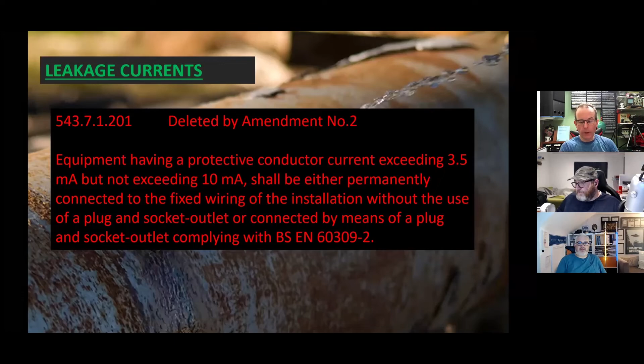But yes, you're right. It does link into this deleted by amendment without a doubt, because it also links into the regulation that covers the leakage on each individual circuit not exceeding 10% of the rating of the RCD. Why would you need 3.5 to 10 milliamp anymore on a reg? You don't need it. So it's effectively gone. There is also one last thing. This one here, this is rowed about so much, guys. 543.7.1.204. It's another UK reg. This has also been deleted, and it's where two protective conductors are used in accordance with 543.7.1.203. The ends of the protective conductors shall be terminated independently of each other. So this is the socket outlets, high integrity earthing.